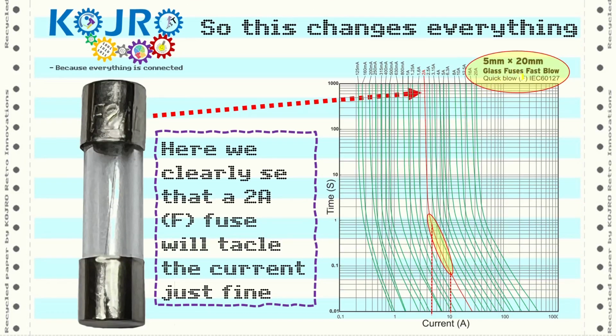F fuses, quick blow fuses - they say they're quick blowing, meaning they don't have the time delay that's actually stated in the other fuses. But even so, if you take the 2 amp fuse here, you see this is the characteristic of this fuse, and down here you have the 4 amps that would have gone into our circuit, and this is the 10 amps at the bottom of the same characteristic and time frame I had on the other curve.